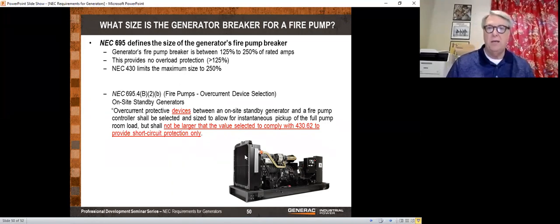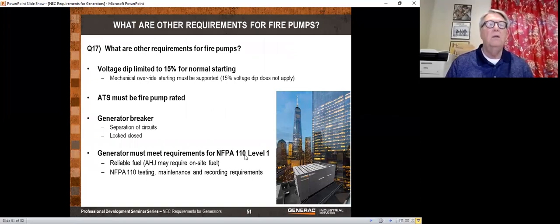And in that case, the voltage dip is limited to 15%. That can be a real difficult situation, especially if you have a Y delta starter, to try to start that thing and maintain no more than a 15% voltage dip. But then you have the backup method, and that's always across the line. In the backup method, you're not limited to the 15%. So you actually have to size your generator twice. Once on your normal method, that would be a reduced voltage starter or a VFD or delta Y or what have you, and then the backup method is across the line. It still has to start it, but it's not restricted to 15%.